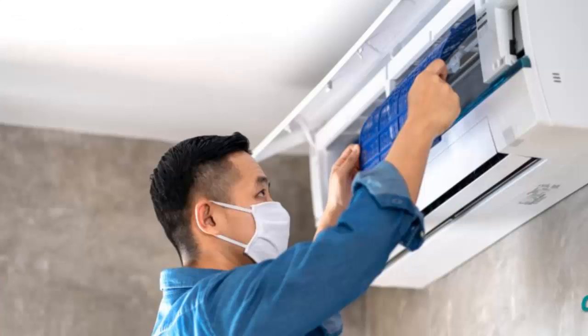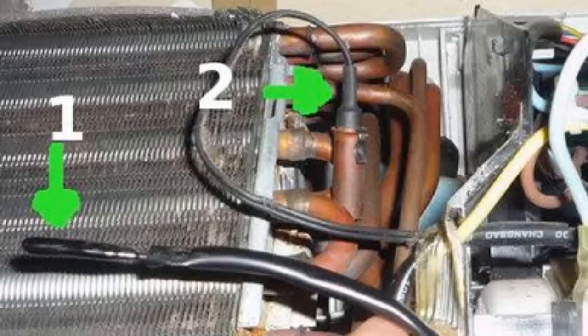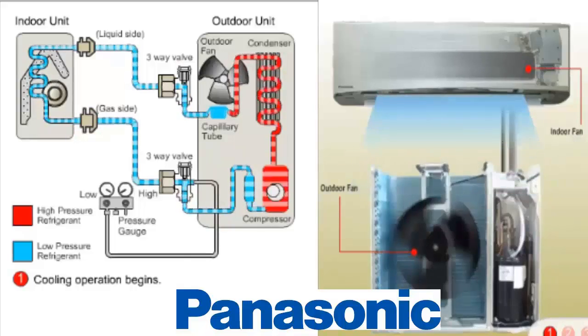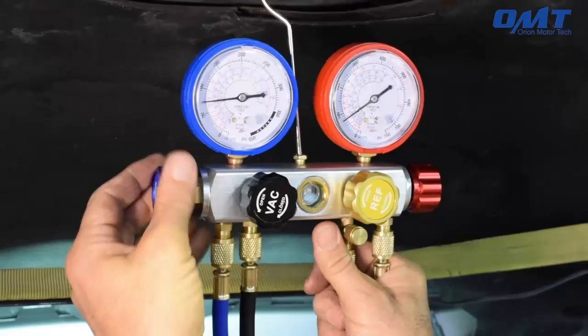Clean and maintain the indoor unit, checking and cleaning filters, the blower fan, and the evaporator. Clean components allow proper airflow and prevent freezing. Confirm that temperature sensors are in their correct locations — an out-of-place or dirty sensor can provide incorrect temperature readings. Measure the resistance of the sensors at a reference temperature provided by the manufacturer to ensure accuracy. If the error persists, measure the system's suction pressure, as low or high suction pressures may indicate a refrigerant problem. Leaks or excessive refills should be addressed.